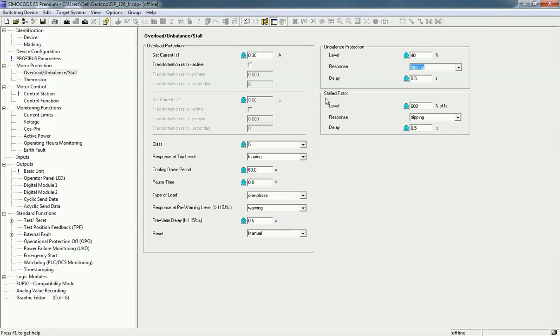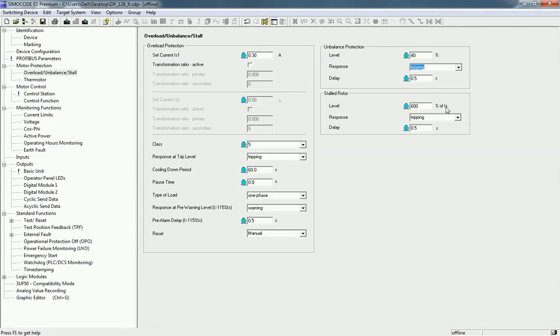For stalled rotor protection — when the rotor is stuck and the set current crosses the limit — you can define the level. When it crosses 600% of the set current and remains for 0.5 seconds, the motor will trip. You can also change this time; for example, if it remains for one second it will trip. This covers the motor protection overload section.